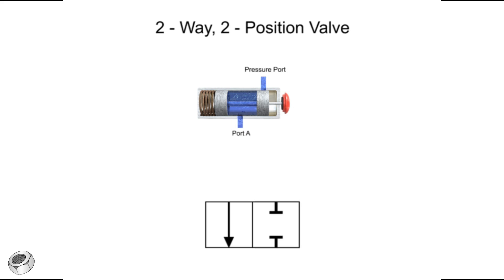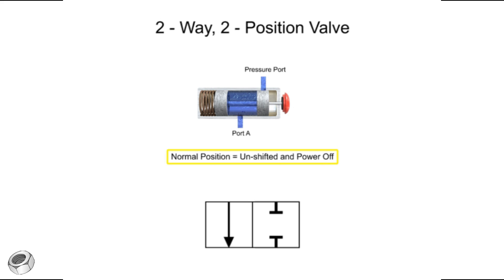Lines are drawn to indicate the normal position of the valve. The normal position is defined as the position of the valve when its spool is unshifted and the power is off. This means that any mechanical actuators, such as springs, are in their non-actuated positions, and electrical actuators, such as solenoids, are powered off. The normal position can sometimes be referred to as the unshifted, de-energized, or unactuated position. In this case, position one is the normal position, so the lines are drawn in the first box.